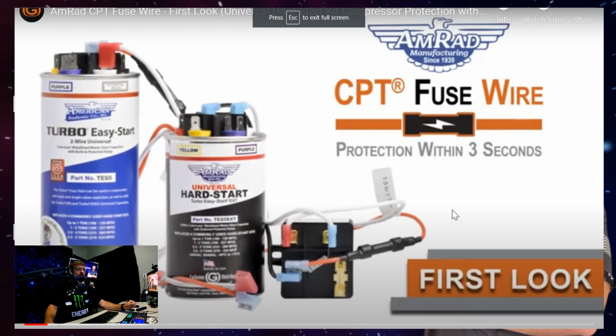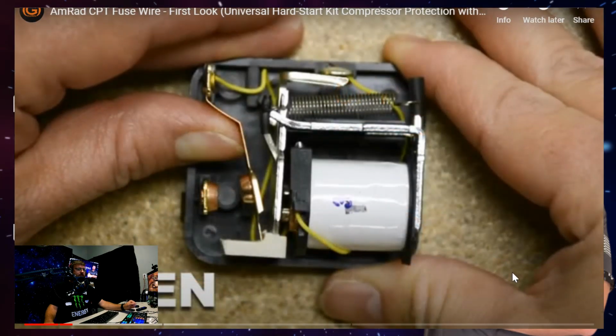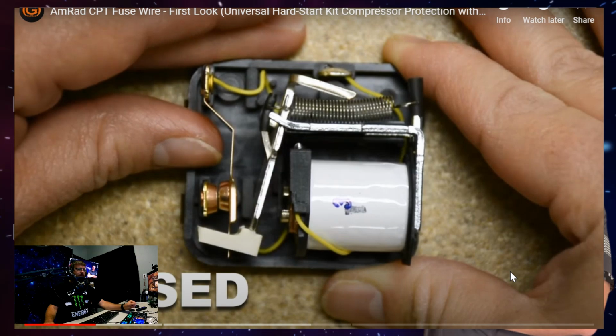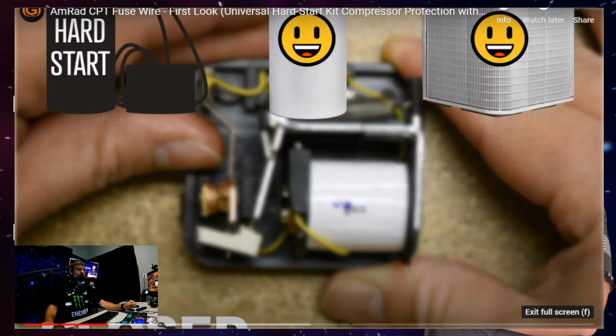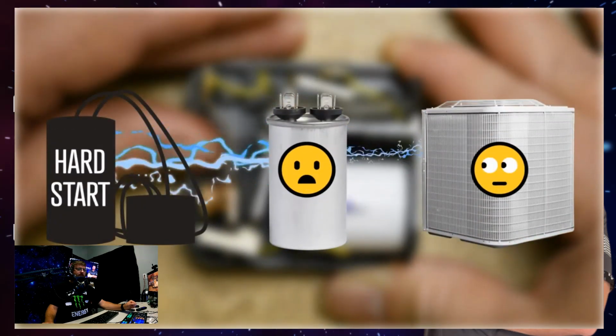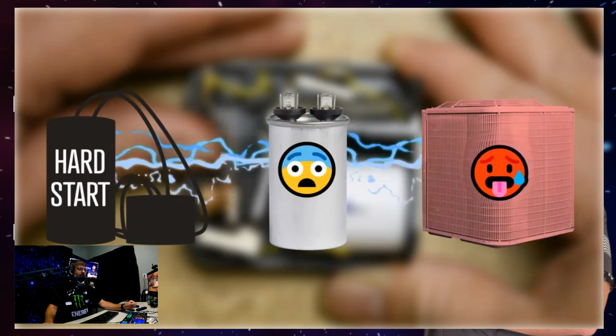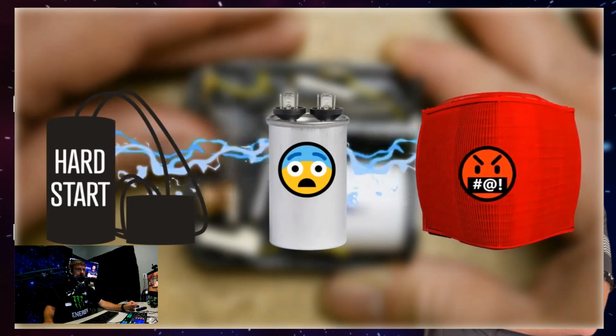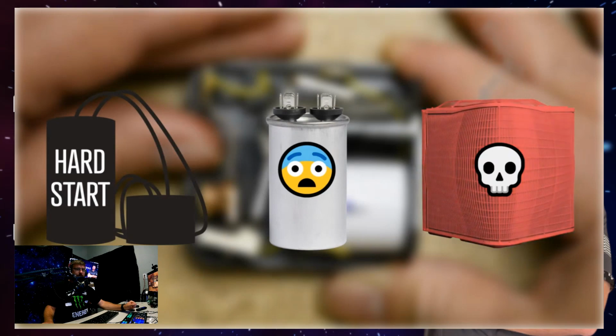See if I can do this. Here's a first look at the best thing to happen to hard start kits since Amrad made them universal. Relay failure can be an issue with hard start kits. When the contact mechanism inside the relay becomes stuck in a closed position, the start capacitor remains in the circuit, forcing the compressor to run with too much capacity. Oh, thanks. Thanks, Amrad. Appreciate it. Or Global, whatever you want to say.